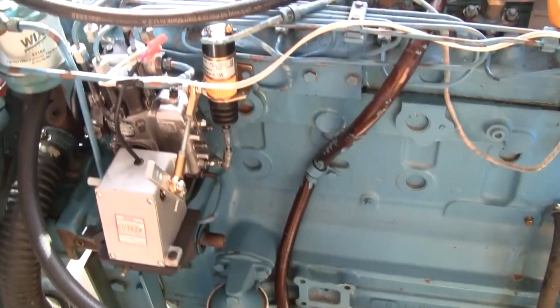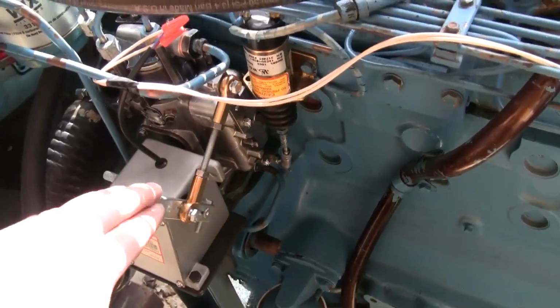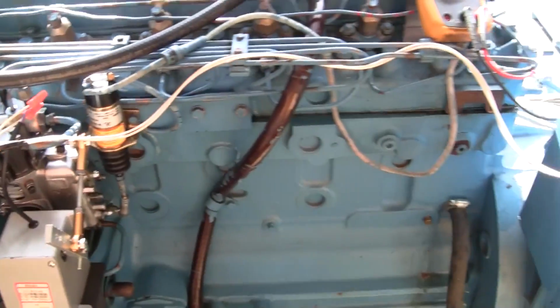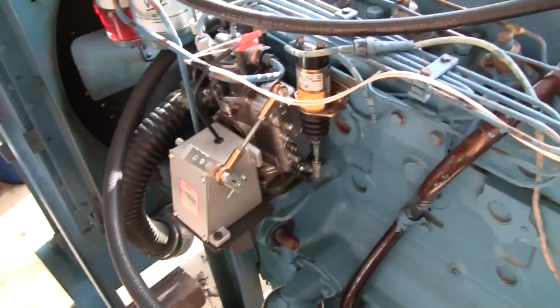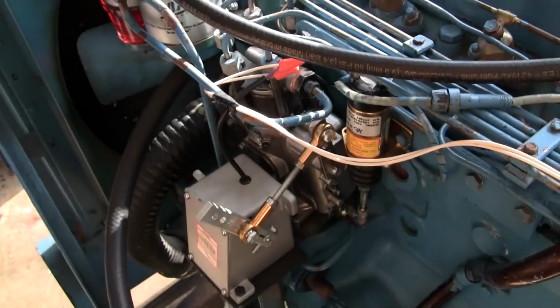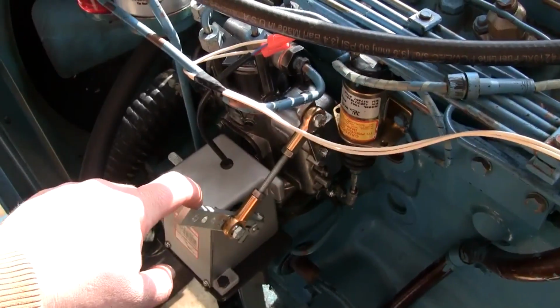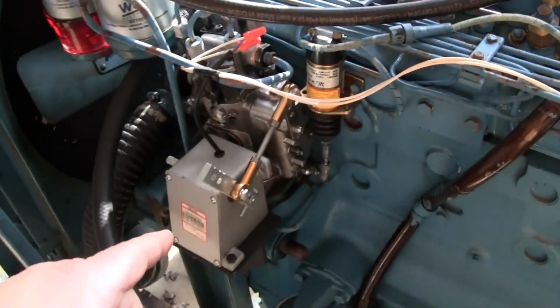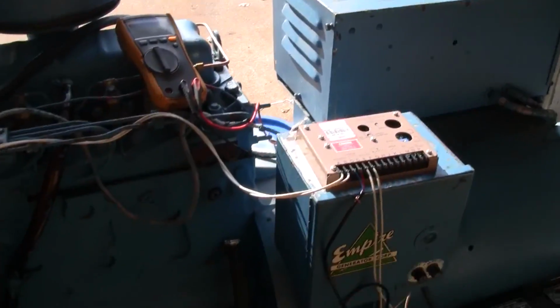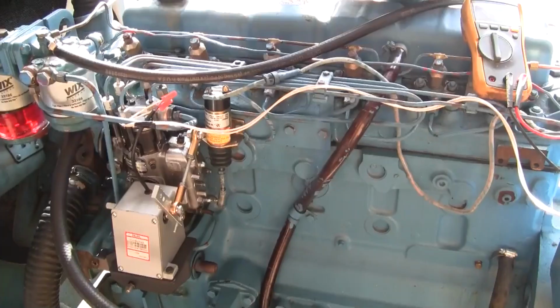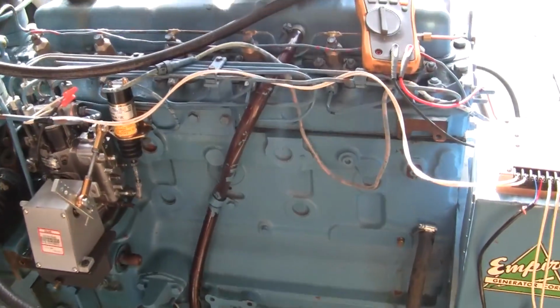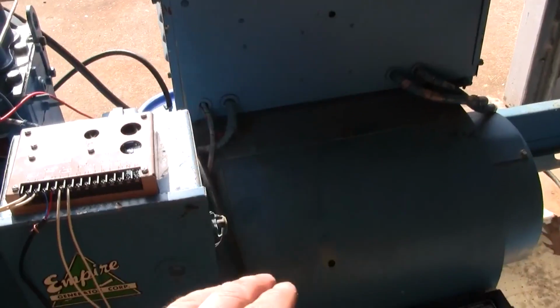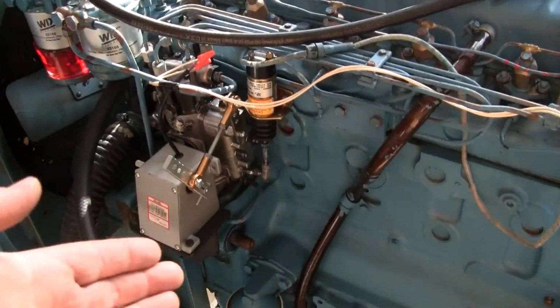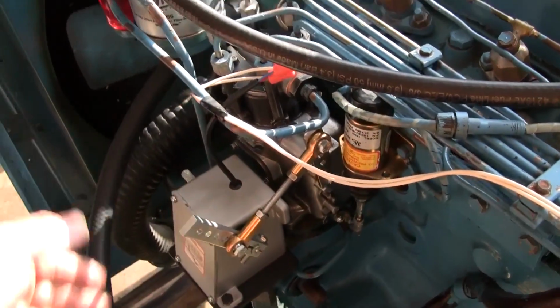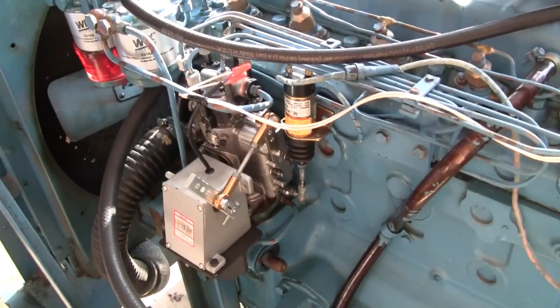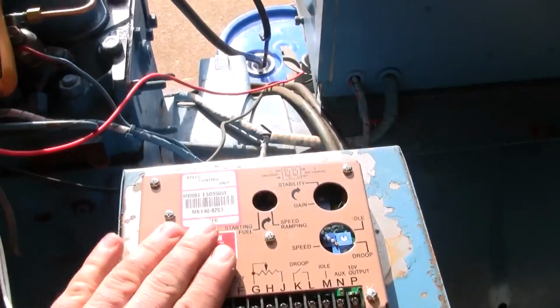Likewise, when that big load comes off, there's going to be a little bit of overshoot. But what matters is it always comes back to 60 promptly and without a lot of bouncing around either. You probably did notice this bouncing around a bit when it was under load. That's because this voltage regulator is not doing its job. We're going from like 238 to 250. That change in voltage is going to change the kilowatt load on the gen set, which in turn is going to change the engine load. And the governor was doing its job, keeping that speed steady. So I'm pretty happy with the performance here.